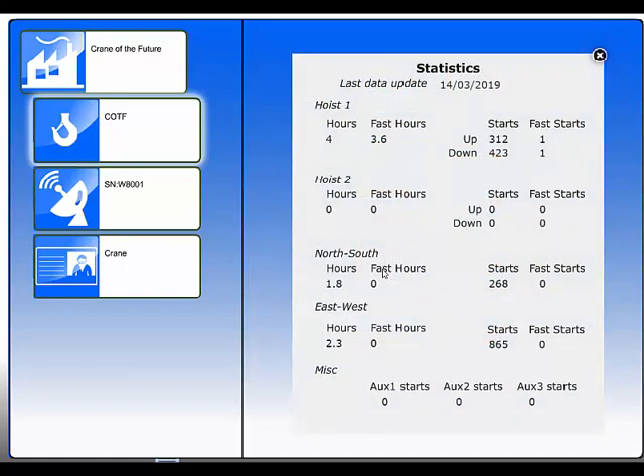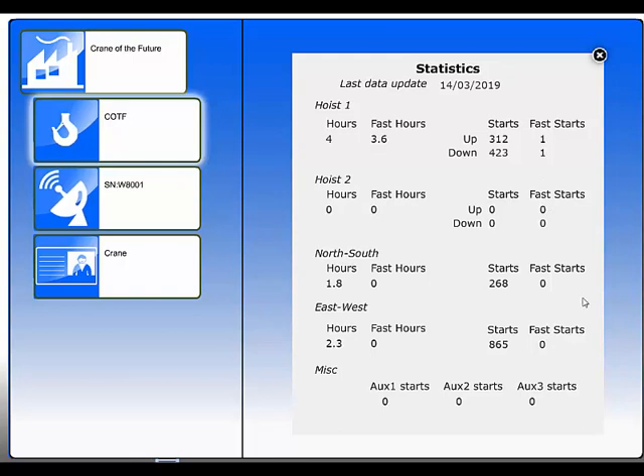Here we give you the number of starts and actuations of each motion, and this is useful if you're trying to figure out why a contactor is wearing out quick, or to know when to change your contactors, or to do preventative maintenance on them. And we also give you the real time hours. This is not scaled according to load spectrum, this is real operating hours of each of those motions, so you can get a feel for how long the motors have run and things like that.